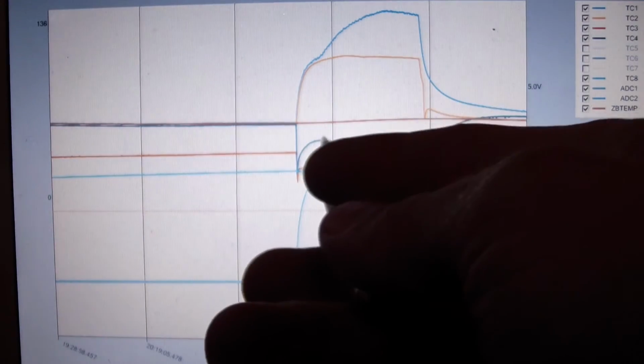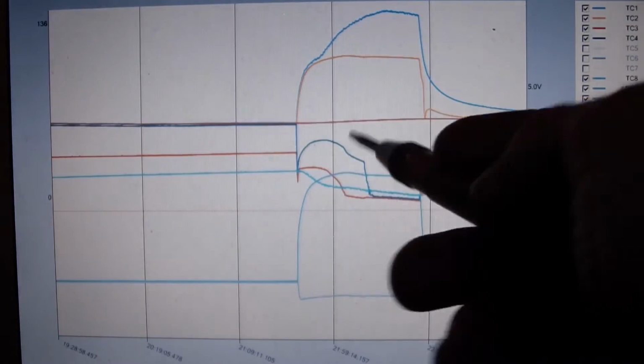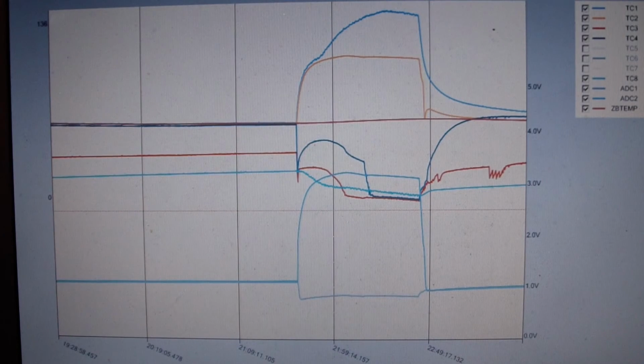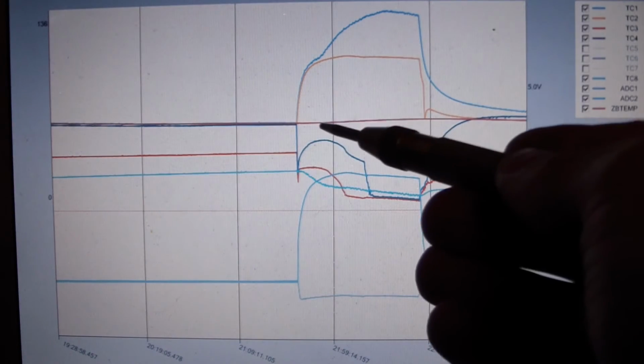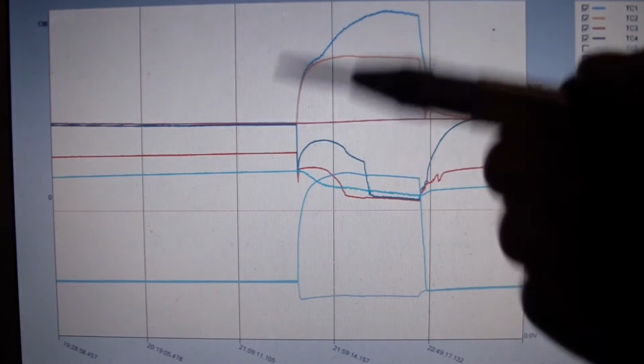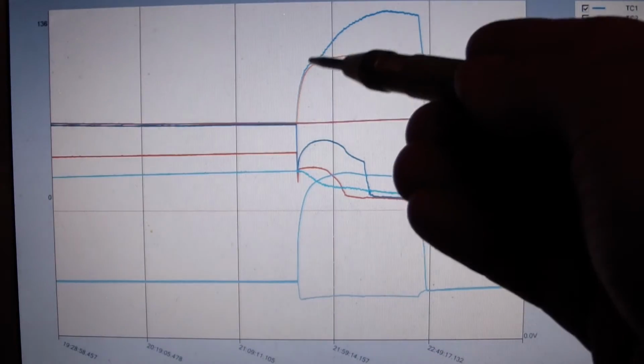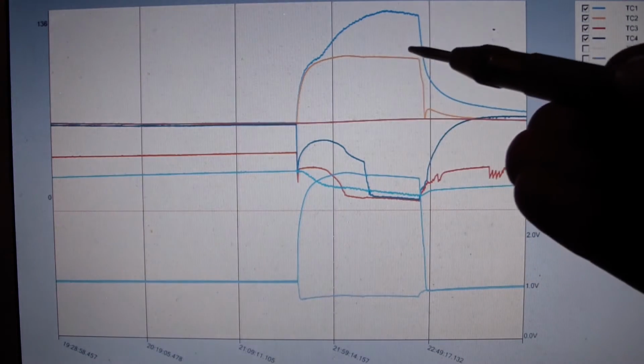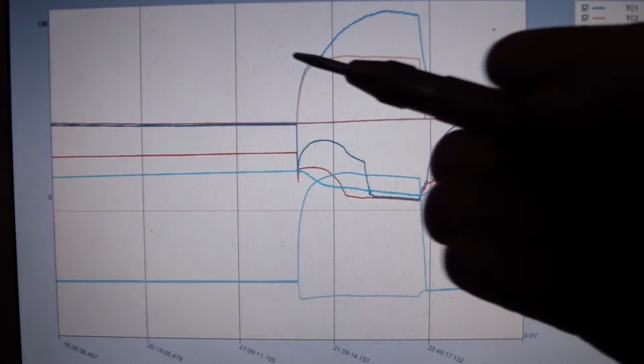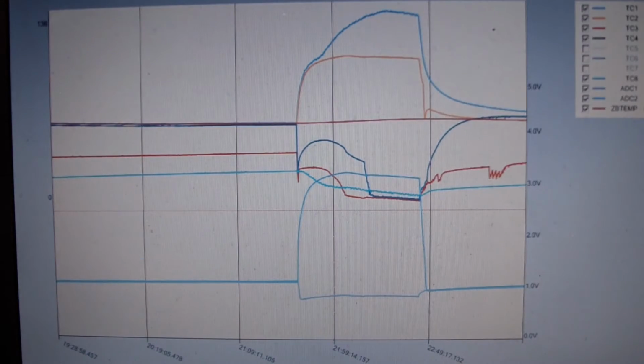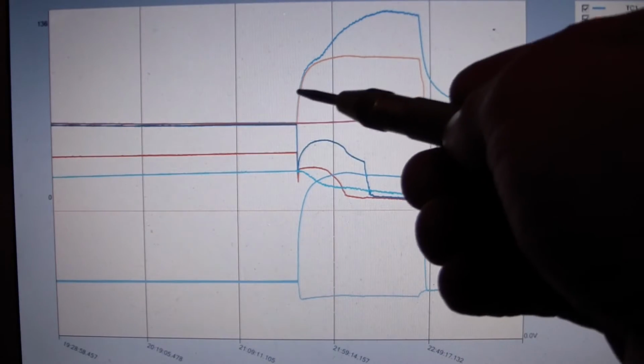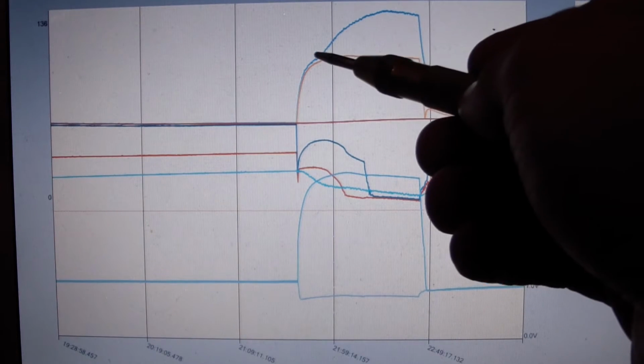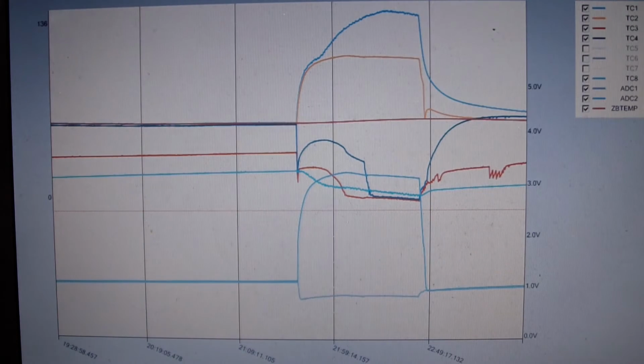One of the next interesting points is about the peak of the superheat on the blue line there, the one right before the compressor. I'd point that out because almost in every example it seems to correspond with these two lines up here and a change that occurs. The yellow line that flattens off right there, that's subcooling after the condenser. The blue one is discharge superheat. And you can see they more or less track one another until about this point here where they separate.